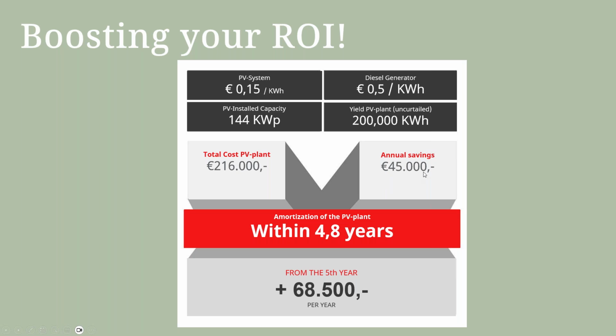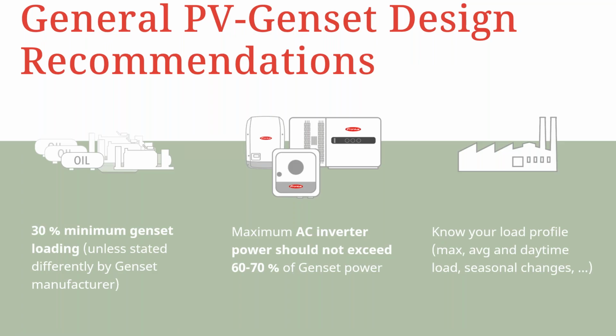So that was the initial annual savings. But then, of course, we know that diesel costs eventually increased, and the annual savings also increased, because with the increase in diesel costs, and of course with the reduction in the consumption of fuel, this will lead to an increase in the annual savings. We have put a bracket of between 4 to 8 years for achieving amortization. But for this particular system, amortization was actually achieved from the 5th year with annual savings of 68,500, just about 70,000 euros per year, which is a very wonderful achievement in that regard.